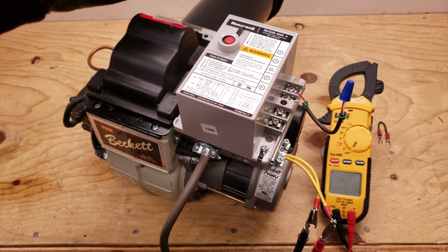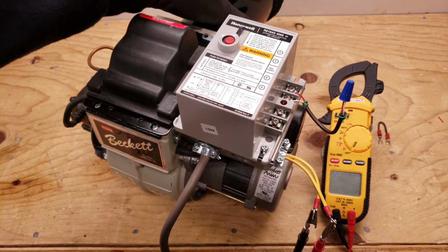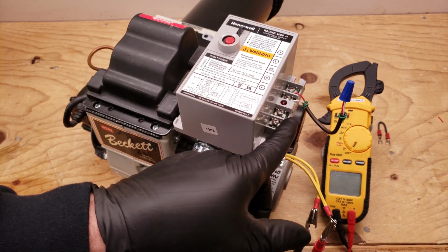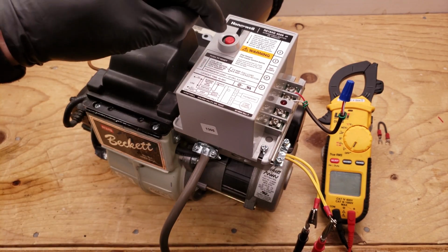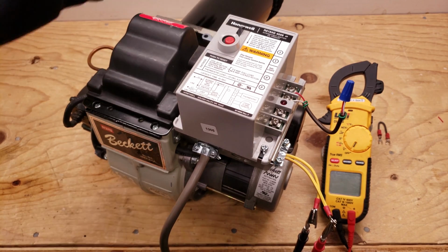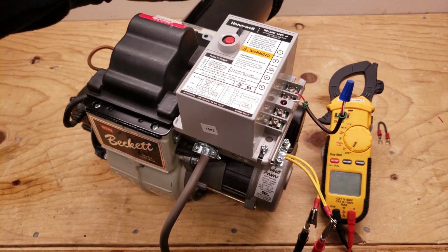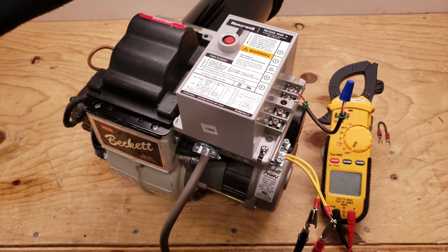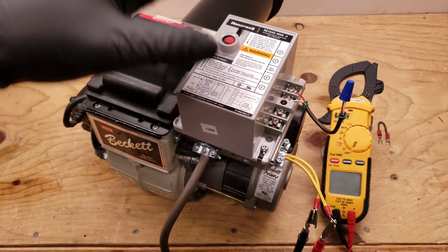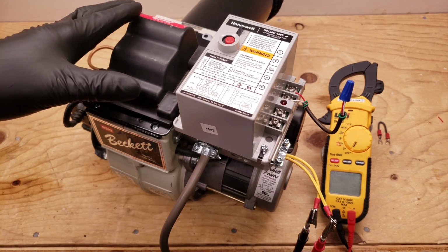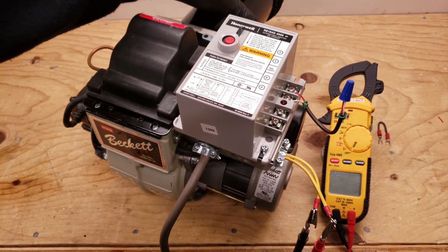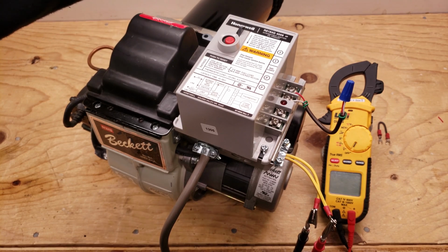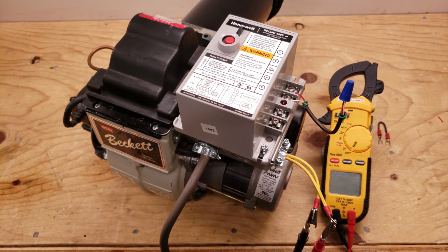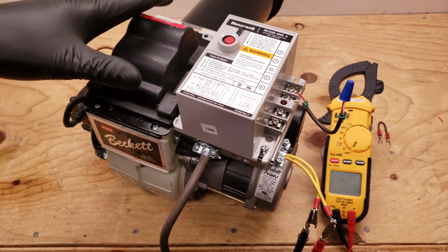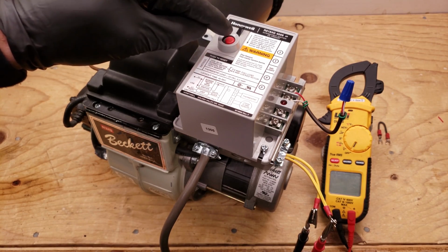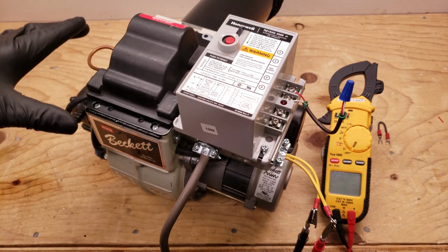So a big problem is maybe that the oil is just not getting ignited and the CAD cell is not seeing any type of flame. So if you just keep pressing this down, you're squirting oil into the heat exchanger and it's not being ignited. So you're going to have a puddling of oil in the heat exchanger, and that's going to be a problem when you do go and finally fix the issue and you have the heat exchanger heating up, and then all of a sudden there's a bang in there due to all that oil getting ignited. So you don't want that to happen. So you want to avoid continually pressing this down. You need to start troubleshooting what the problem is.